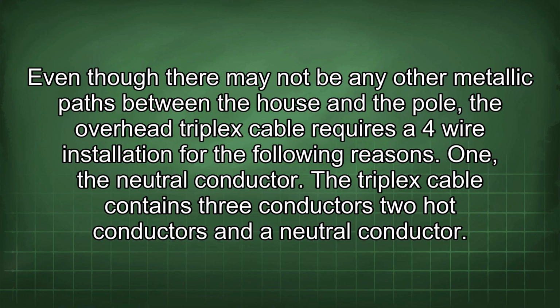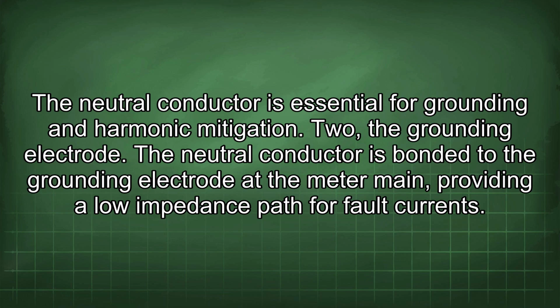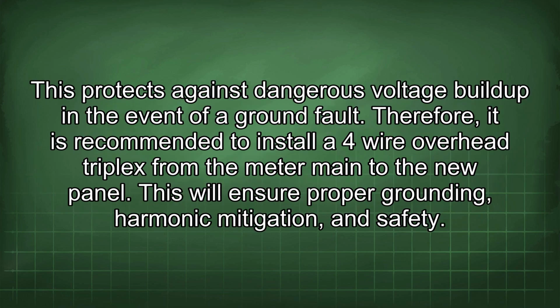1. The neutral conductor. The triplex cable contains 3 conductors, 2 hot conductors and a neutral conductor. The neutral conductor is essential for grounding and harmonic mitigation. 2. The grounding electrode. The neutral conductor is bonded to the grounding electrode at the meter main, providing a low impedance path for fault currents. This protects against dangerous voltage buildup in the event of a ground fault.